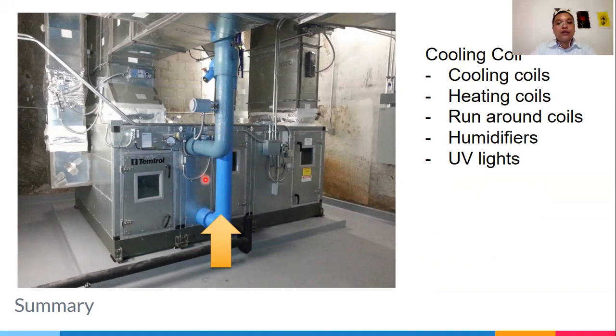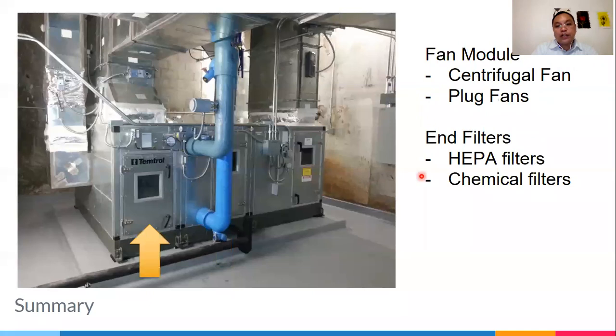For the coil, we have different kinds of coil: cooling coil, pre-cooling coil, run-around coil, depending on your temperature requirement and your application requirements, on how you will achieve your design condition. Before the coil and after the filter, sometimes you would need UV lights. After the coil, you would put your humidifiers. After the humidifiers, we have the fan section.